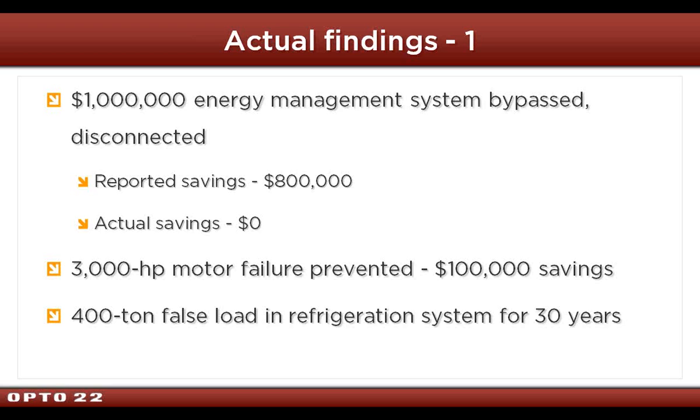Meatpacking plant, the one that was spending 5 times what it should. We got into it. I got a call from the engineer from the utility company. They were preparing to spend $100,000 for more transformers to add more chillers because they were out of cooling. They were having a real problem with keeping the meat cool and keeping everything cool in the summertime. The data from our system showed that they had almost 3 times the amount of cooling they needed already installed. I met with the president and the plant manager. They said, we haven't been able to cool this plant properly for 30 years.